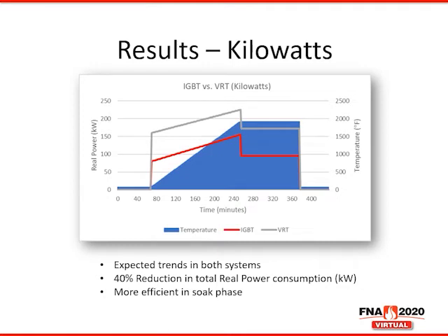Here are the results for our case study. First, let's look at kilowatts. The graph here shows the comparison of kilowatt usage of the VRT versus our IGBT MFDC power supply. Let's break down this graph here. On the left, the y-axis is real power measured in kilowatts. And on the right, we have a secondary y-axis that shows temperature in degrees Fahrenheit. This is what was shown on the previous slide, where we ramp up to a 1900 degree soak phase.